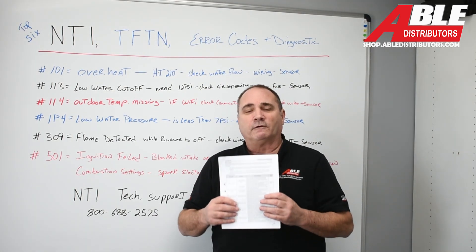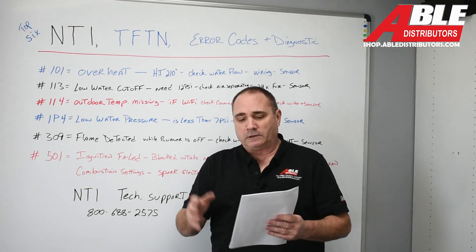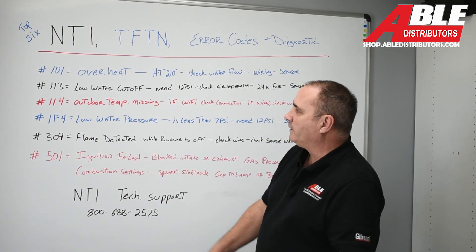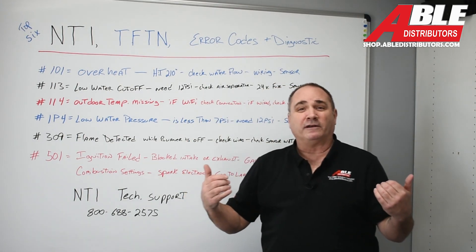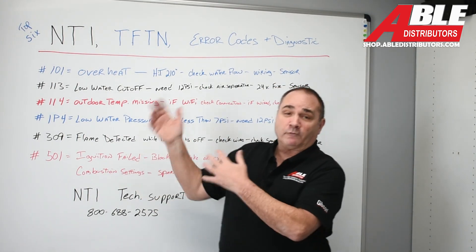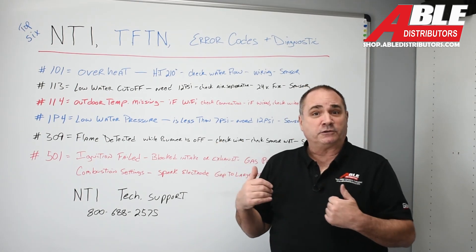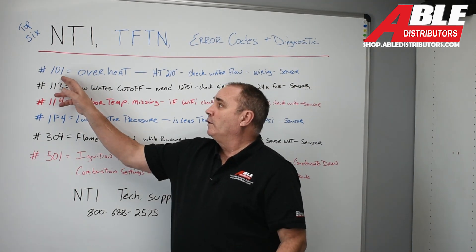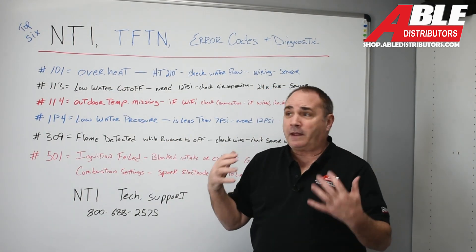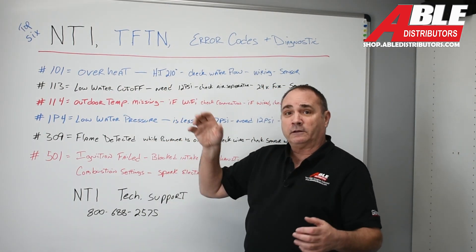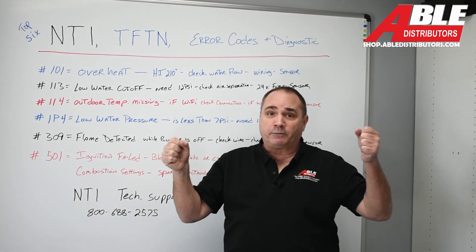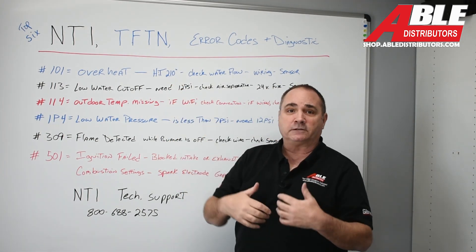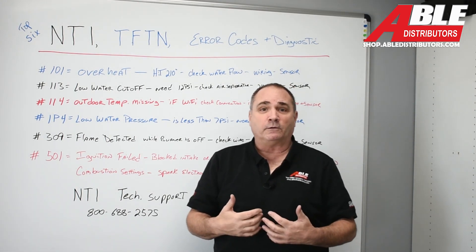NTI puts together a very, very good manual — one of the best, probably. They have a few pages of error codes, and I went through and picked out the ones you might run across and what you would check. Error code 101 is an overheat. That means the boiler, either on the outlet pipe or the inlet pipe or both, hit 210 degrees — obviously it's gonna lock itself out. It's way too hot.